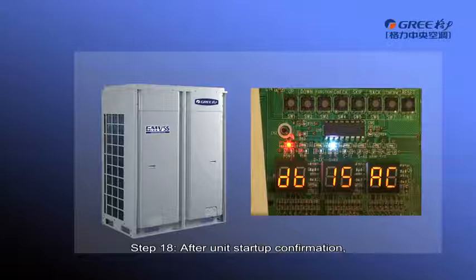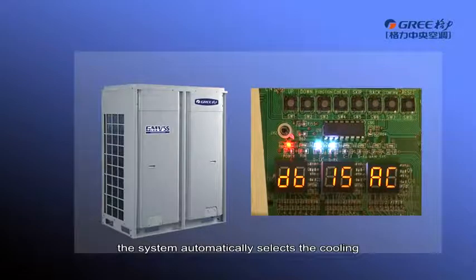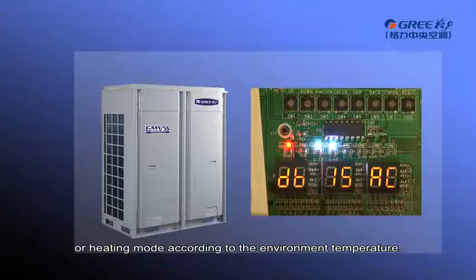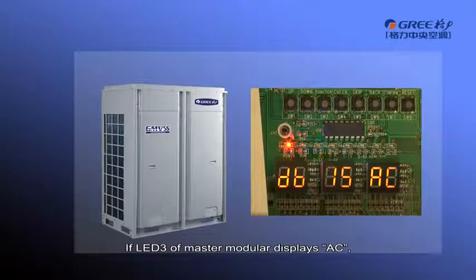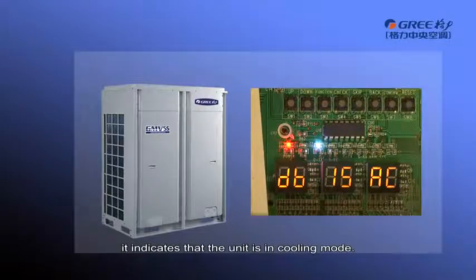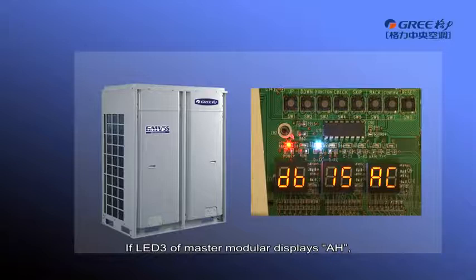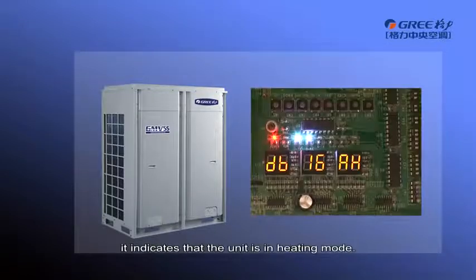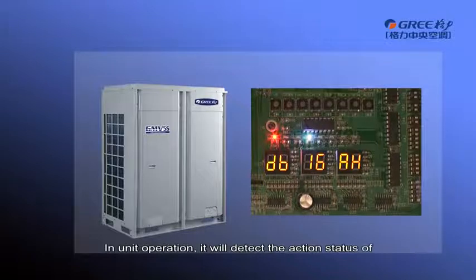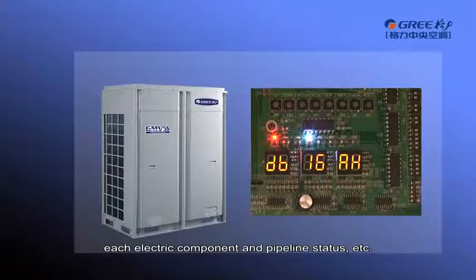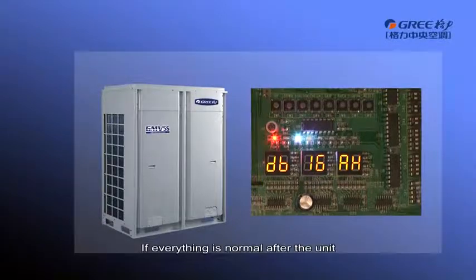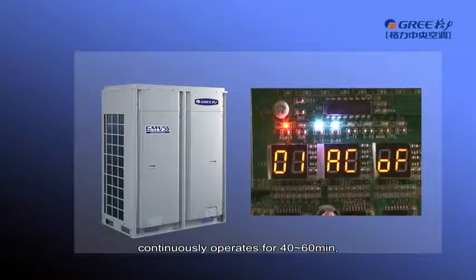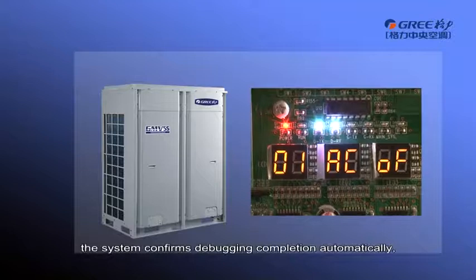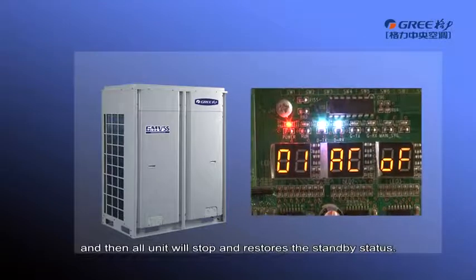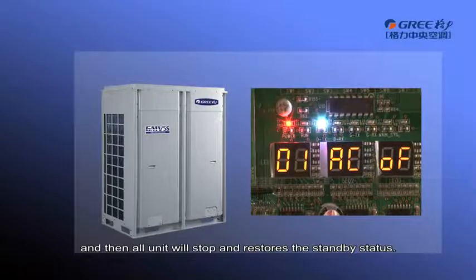Step 18. After unit startup confirmation, the system automatically selects the cooling or heating mode according to the environment temperature. If LED 3 of master unit displays AC, it indicates that the unit is in cooling mode. If LED 3 of master module displays AH, it indicates that the unit is in heating mode. In unit operation, it will detect the action status of each electric component and pipeline status, etc. If everything is normal after the unit continuously operates for 40 to 60 minutes, the system confirms the debugging completion automatically, and then all unit will stop and restore the standby status.